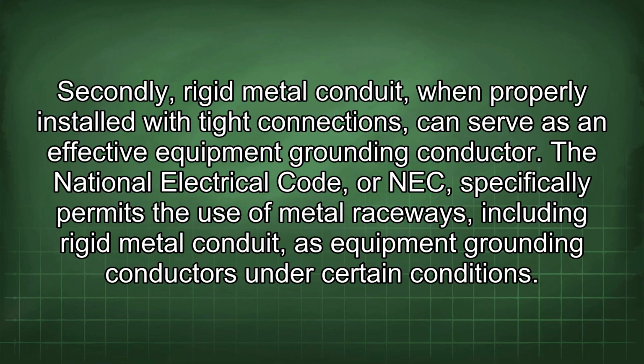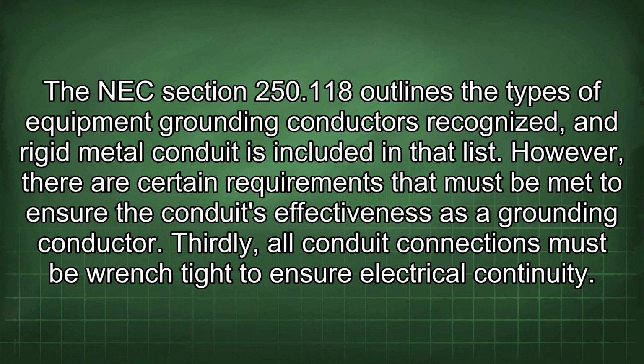The National Electrical Code, or NEC, specifically permits the use of metal raceways, including rigid metal conduit, as equipment grounding conductors under certain conditions. NEC Section 250.118 outlines the types of equipment grounding conductors recognized, and rigid metal conduit is included in that list. However, there are certain requirements that must be met to ensure the conduit's effectiveness as a grounding conductor.